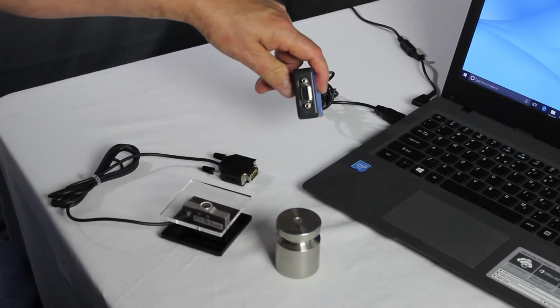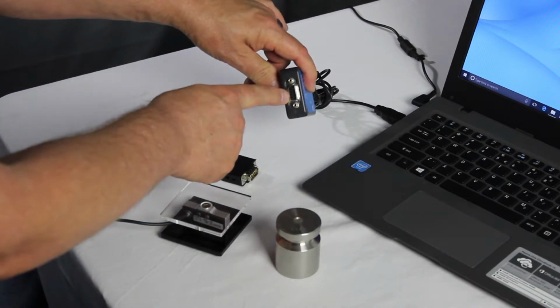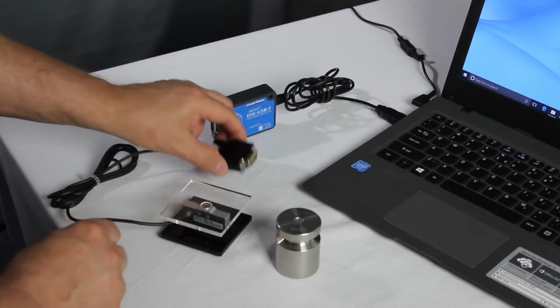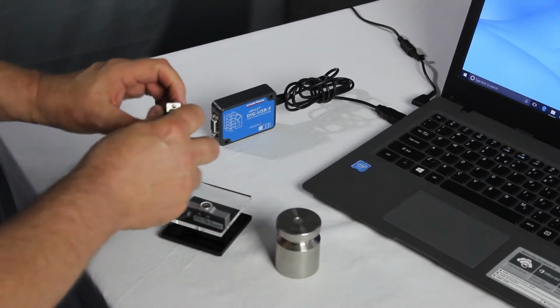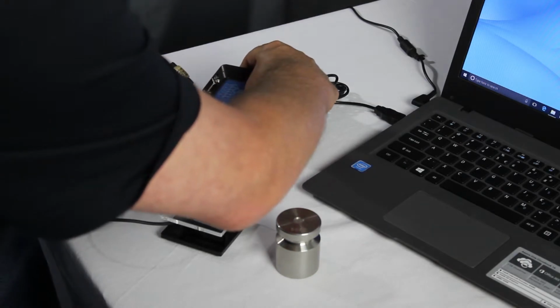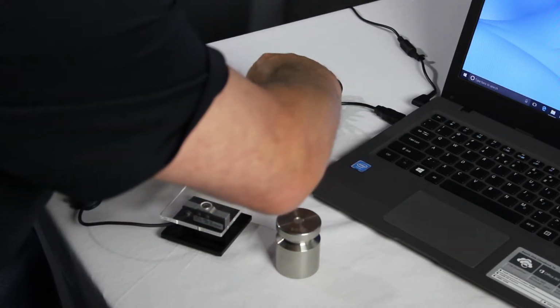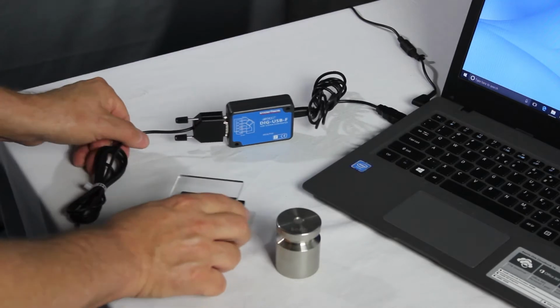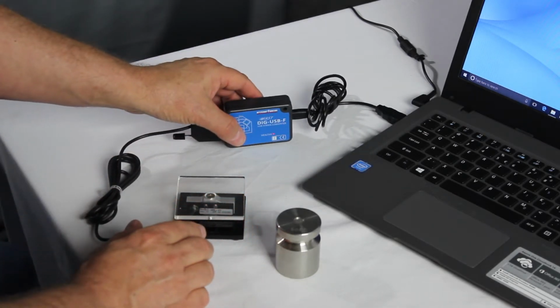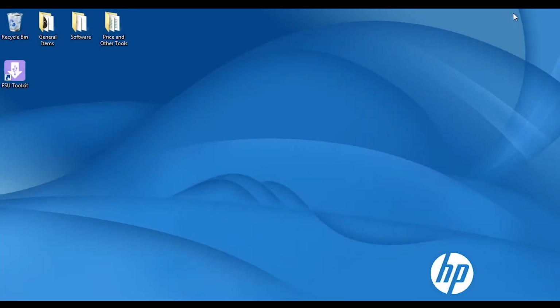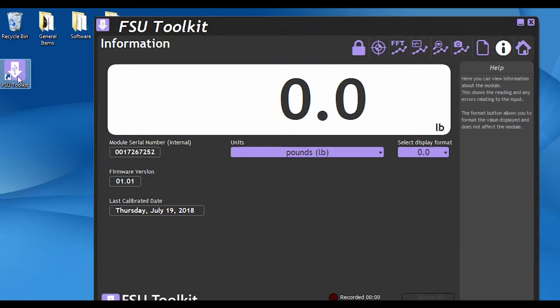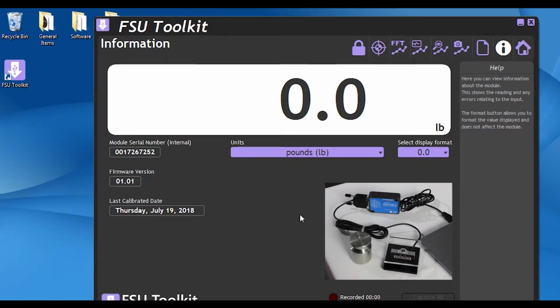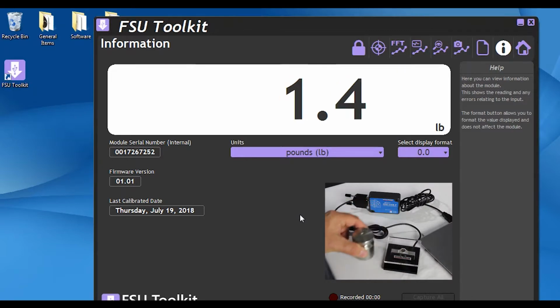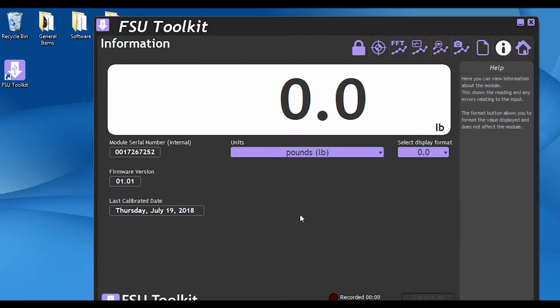On the end, it has a 9-pin female D-type connector. So your load cell will have to have a 9-pin male D-type connector. Now everything is connected up. Okay, now we're going to open the FSU toolkit for the DIG USB-F and make sure we have good communication between the load cell and through the instrument, and it's working fine.